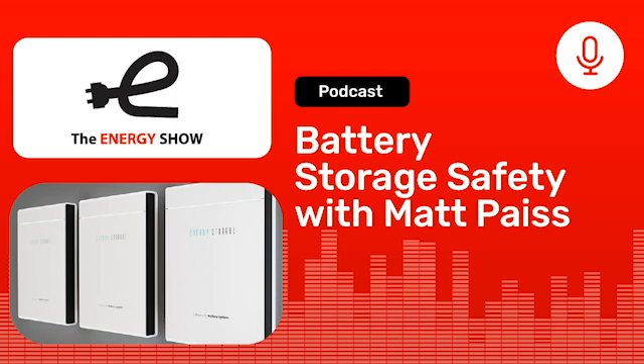A residential system is obviously much smaller. A single unit will typically be less than 20 kilowatt hours, and homeowners could have one to many batteries depending on the size of the house and what they need. Commercial batteries are typically used in light industrial to utility scale, and could be large cabinets, 40-foot shipping containers, or an entire building filled with racks of batteries, like we have down in Moss Landing, which is the largest battery in the world — it fills a 900-foot long, 3-story building with close to 5,000 battery racks. Commercial systems typically involve a lot more communications equipment and larger inverters to get up to the larger voltages needed, and typically environmental controls like HVAC. So there's a lot more equipment involved on the commercial side.